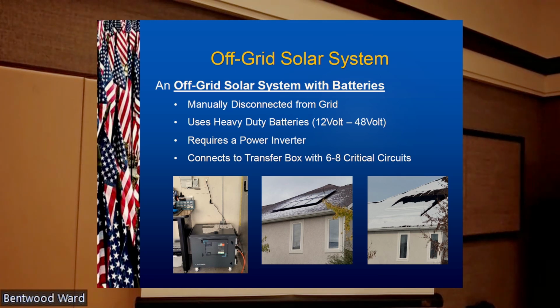So it doesn't work for two reasons. First, your solar system will shut down when there's no grid power, if you're purely grid-tied and don't have battery backup - that's specifically to prevent you from heating up the lines when they're down and a lineman is working on them. What you're talking about is trying to hack around it, put your Generalink on so you trick your inverter into thinking you're on the grid. Unfortunately that doesn't work, for two reasons. One, most inverters are looking for a specific wave coming off the grid, which the generator doesn't provide. Secondly, even if you could trick it into working, you'd be producing power from your generator and your panels at once, and unless you're consuming every watt of that power, you'd overload your inverter or your solar panels.